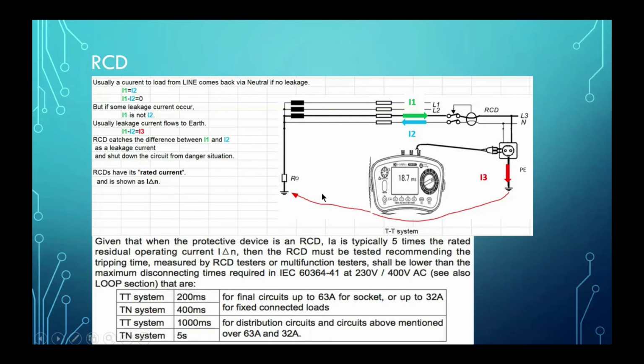Okay. Then the tripping currents and tripping times, if you follow the IEC standard, there is a standard to follow. For example, for final circuits up to 63 amp for socket outlet or up to 32 amp for fixed connected load, in the TT system and TN system, the requirements are different. It must be lower than 200 millisecond, or 400 millisecond for TN system. It's very fast.